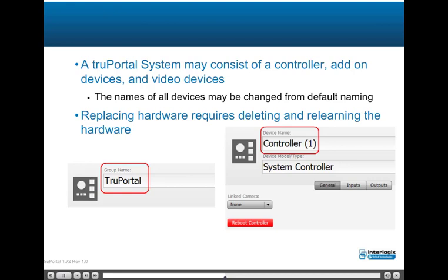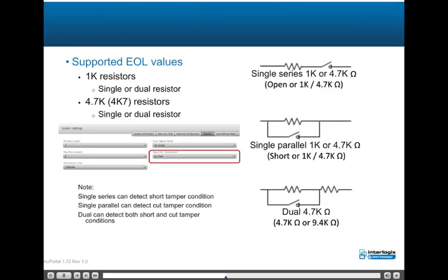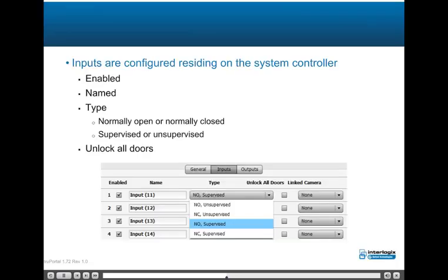A TruPortal system may consist of a controller, add-on devices, and video devices. The names of all devices may be changed from default. Replacing hardware requires deleting and relearning the hardware. TruPortal supports five end-of-line resistor types: 1K resistors (single or dual) and 4.7K resistors (single or dual). Inputs are configured on the system controller and may be enabled, named, and type configured. Input type is configured as normally open or normally closed, and supervised or unsupervised, with an option to unlock all doors if the alarm input is from an alarm or emergency system.